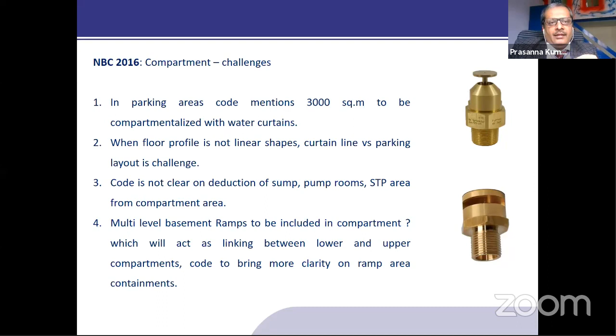The second thing on the parking level is the structural system - I'm touching on practical things here. The structural system has capitals and beams. When we put the water curtains, they cannot be taken to the highest level of the slab because of limitations. So when we limit it, the wide angle of opening of the water curtain creates a gap above the water curtain line, where smoke and fire could spread to the next compartment.